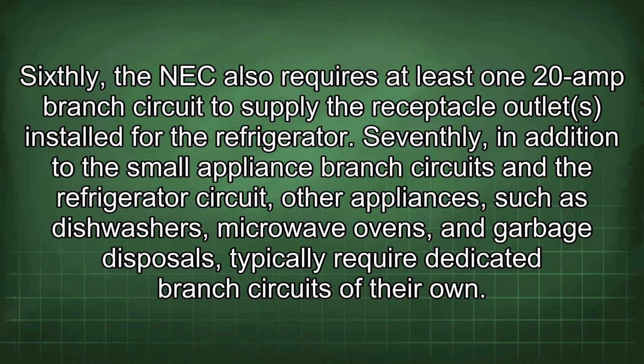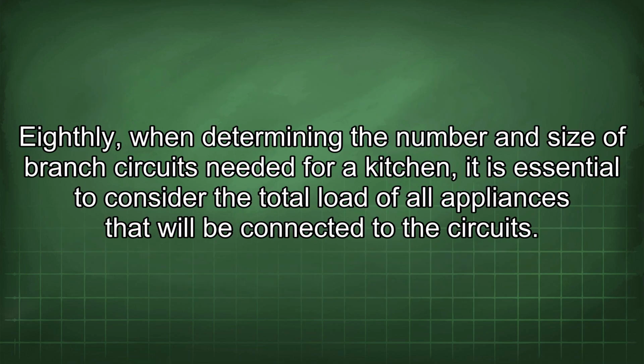Sixthly, the NEC also requires at least one 20 amp branch circuit to supply the receptacle outlet installed for the refrigerator. Seventhly, in addition to the small appliance branch circuits and the refrigerator circuit, other appliances, such as dishwashers, microwave ovens, and garbage disposals, typically require dedicated branch circuits of their own. Eighthly, when determining the number and size of branch circuits needed for a kitchen, it is essential to consider the total load of all appliances that will be connected to the circuits.